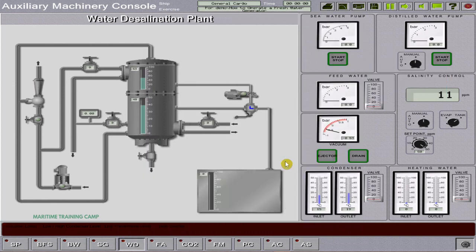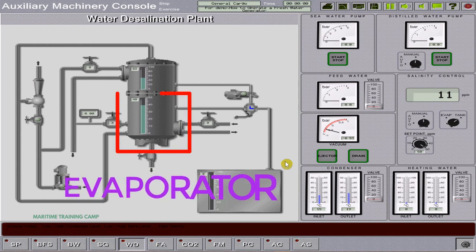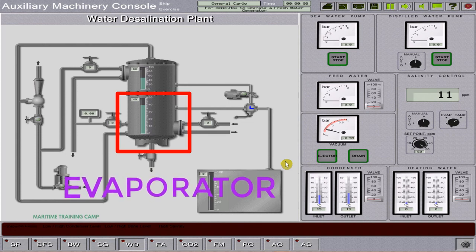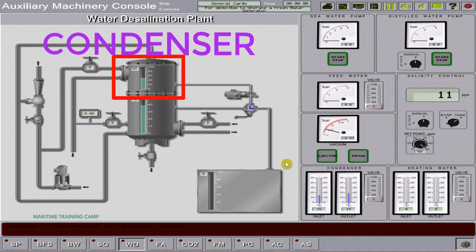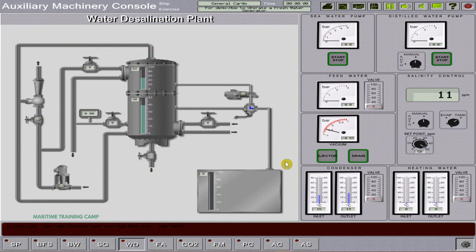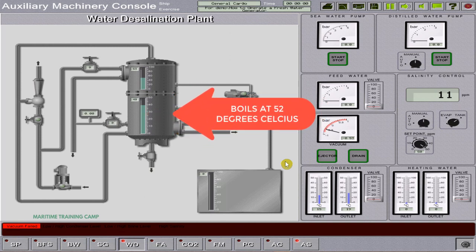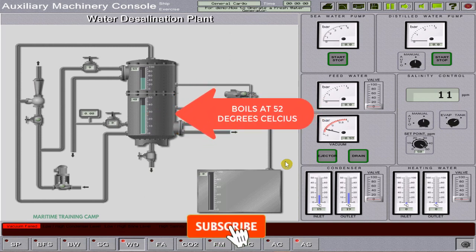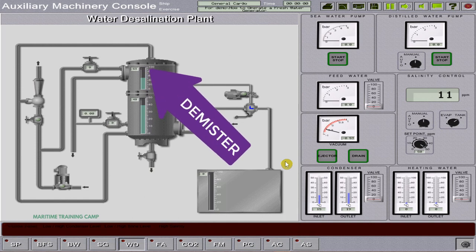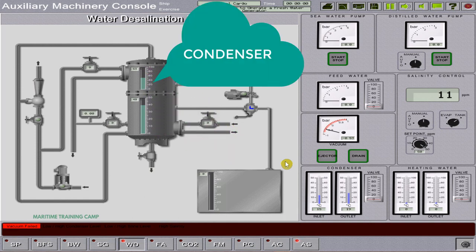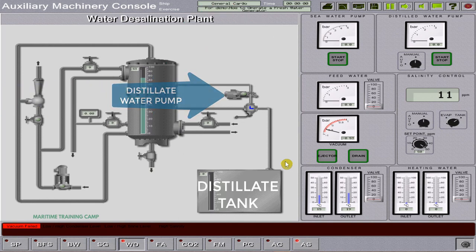The distiller includes heat exchangers which perform the function of an evaporator, located in the bottom part of the diagram, and a condenser, located at the top part of the diagram. Due to high vacuum — 85 to 90 percent — the brine in the evaporator boils at a temperature of 52 degrees centigrade. The vapor rises and passes through the demister, where it rids itself of water admixture and is fed to the condenser, where it is cooled with seawater and the vapor is condensed.